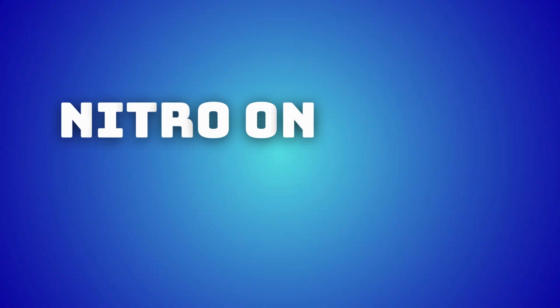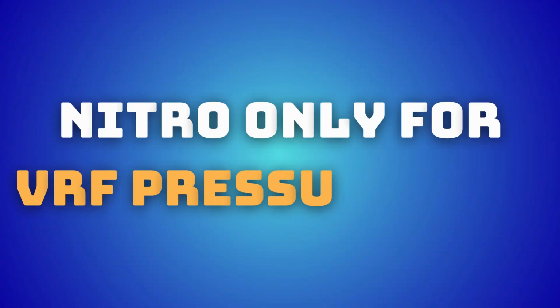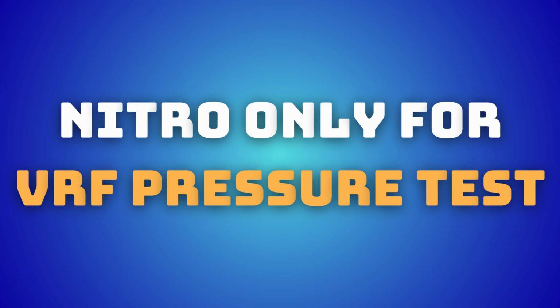For doing a pressure test, we don't want trace gas in there. That's going to allow way too much fluctuation. And this is another great opportunity that you could evacuate. We're not talking pull a full evacuation on the system. We're talking about just pulling a little bit of the atmosphere or whatever is in there off. Make sure all the refrigerant gases are out. You'll get a much more stable pressure test overall, especially over a 24-hour span.